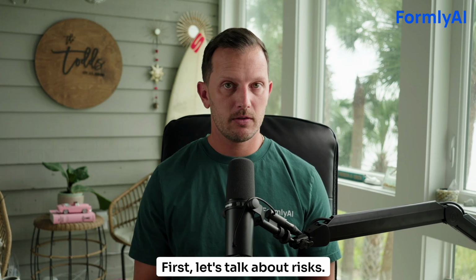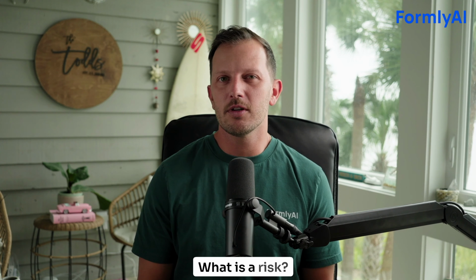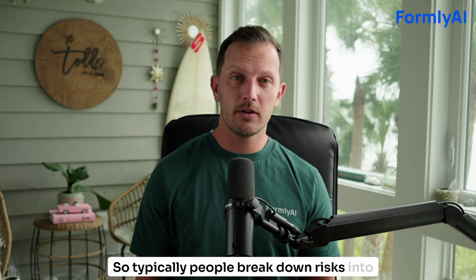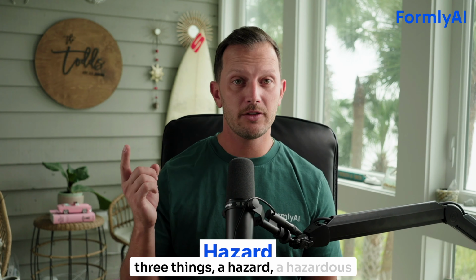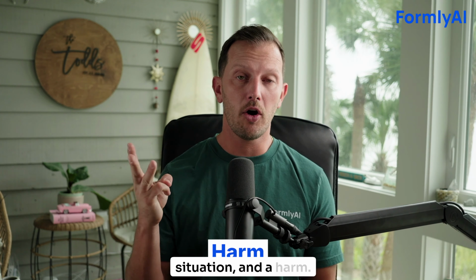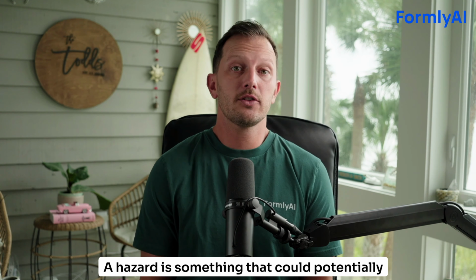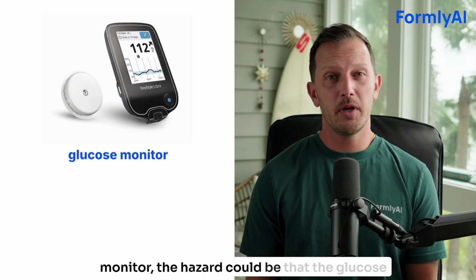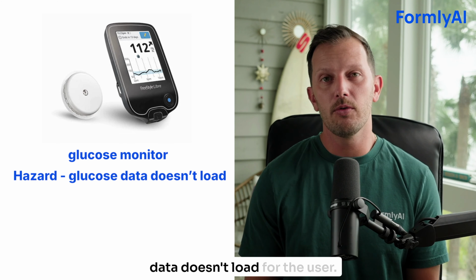First, let's talk about risks. What do they actually look like? What is a risk? So typically people break down risks into three things: a hazard, a hazardous situation, and a harm. A hazard is something that could potentially go wrong with a device. So let's take an example device, for instance. Let's say we have a glucose monitor. The hazard could be that the glucose data doesn't load for the user.